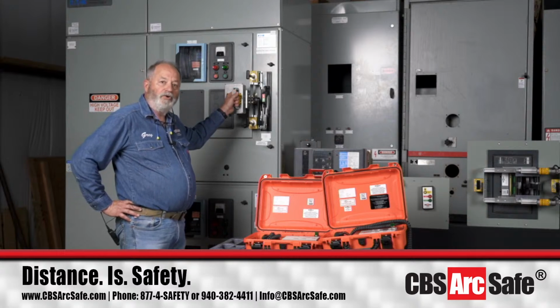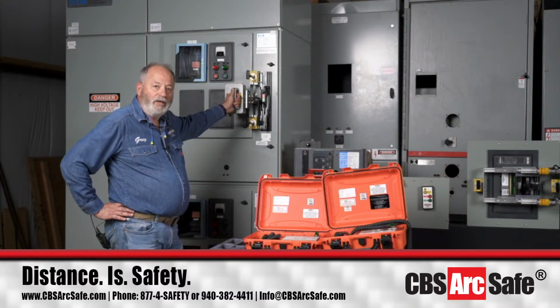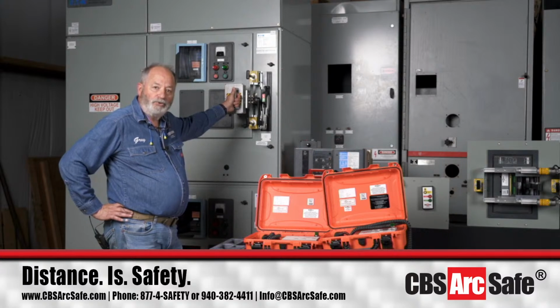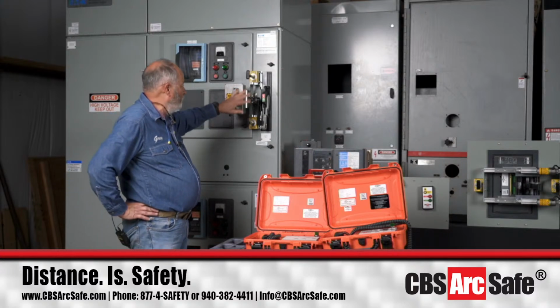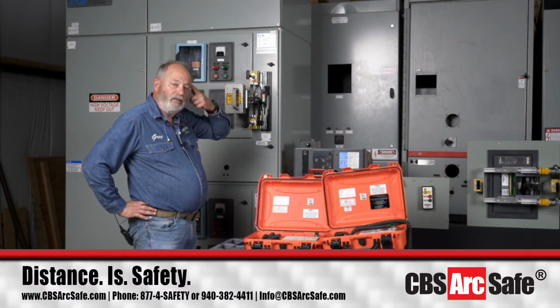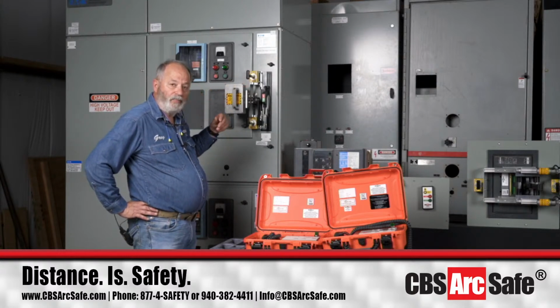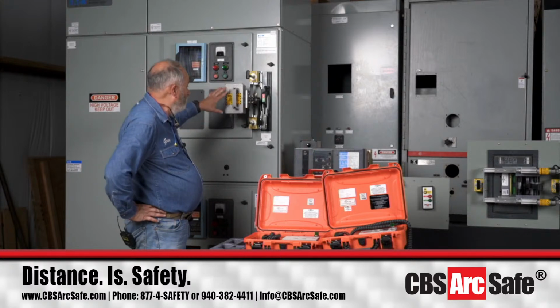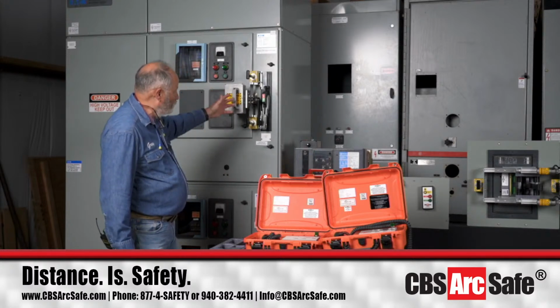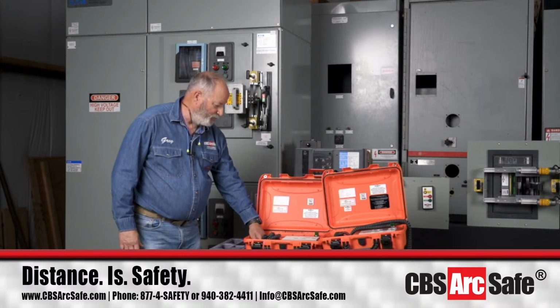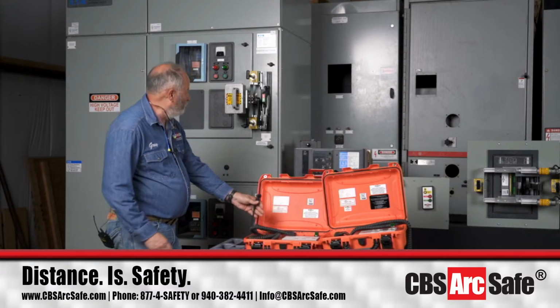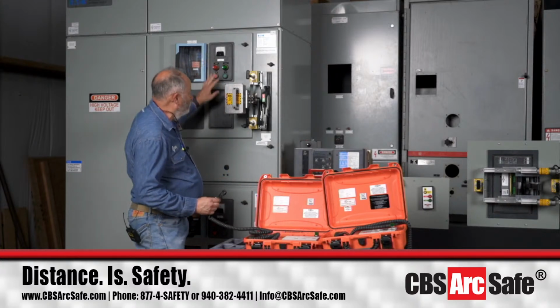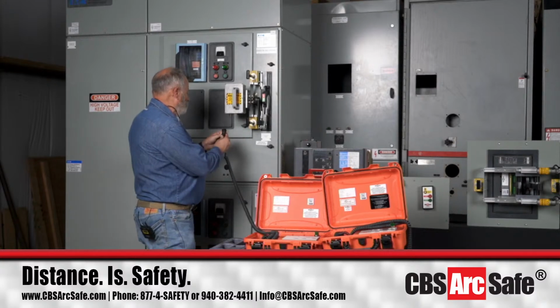One thing to note is there's also a current generation Ampgard load break switch, which looks similar to this, but is a different item altogether, not one of the motor control centers. We use the RSO1 to operate this. So we've got this in place, and you'll notice we don't have to open the low voltage door to be able to use it.